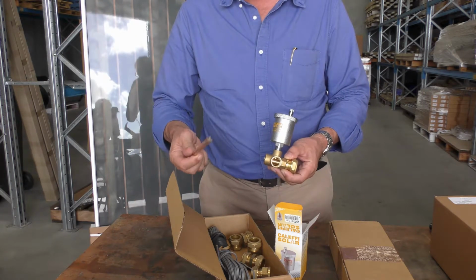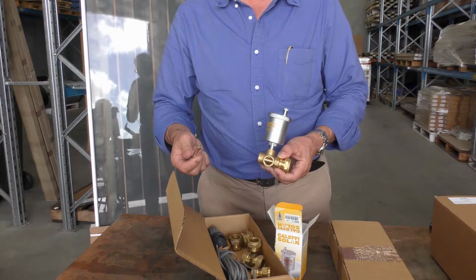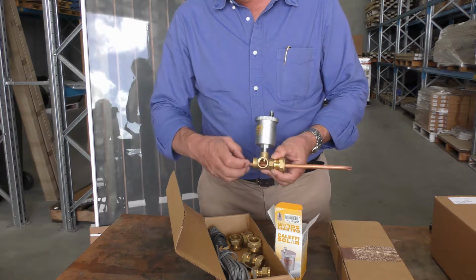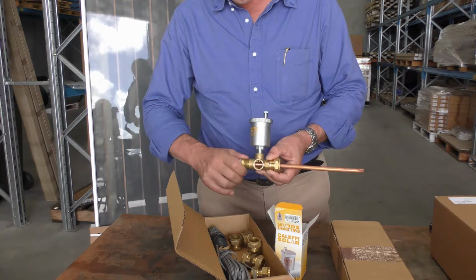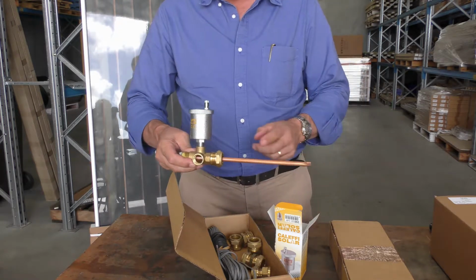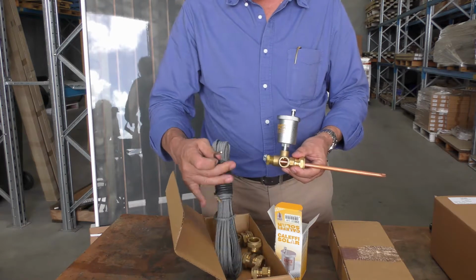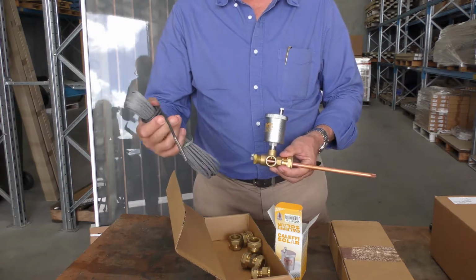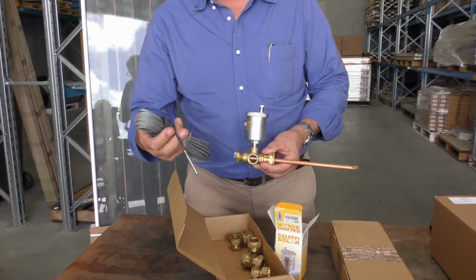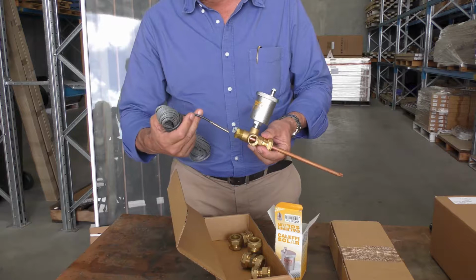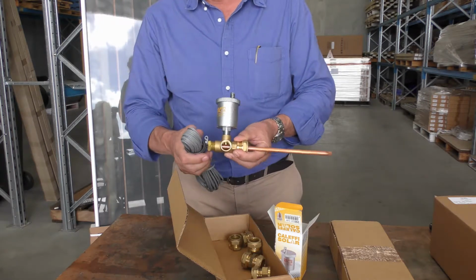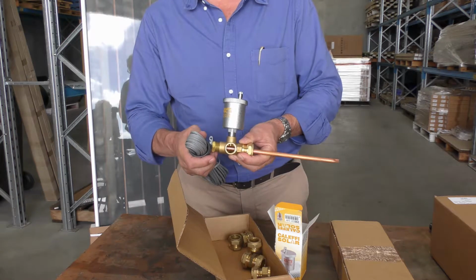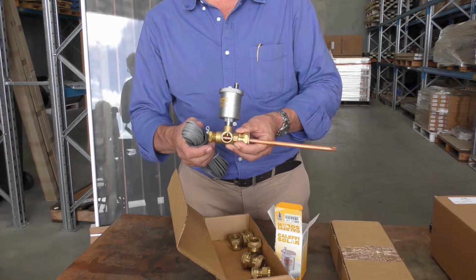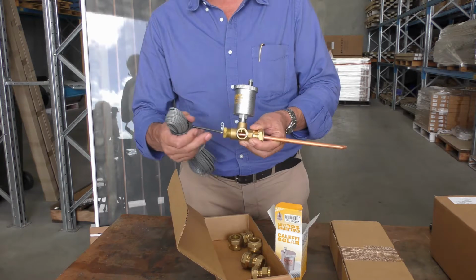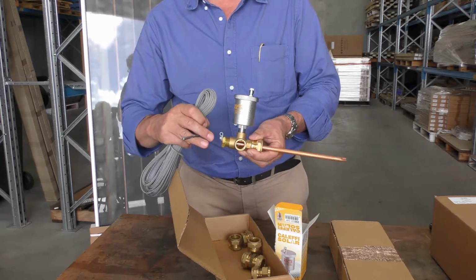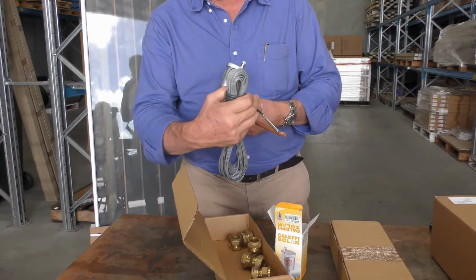Now the idea of this is we're going to talk a little bit about the thermistors or the sensors that we use. This goes into your HotCon and screws up in there, and again that goes into the collector, and that would then have our hot sensor, which is a PT1000 temperature sensitive thermistor. And that slides into there to ensure that we measure the temperature in the collector at the most valuable location, not connected to the outside, so you're only picking up a part of the real temperature of the collector, but it's actually located all the way to the end of it here.